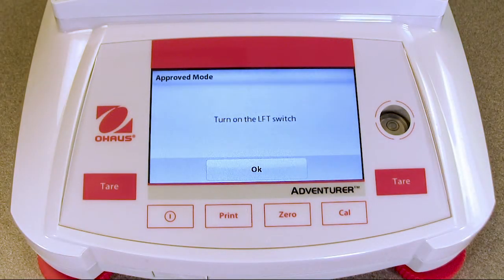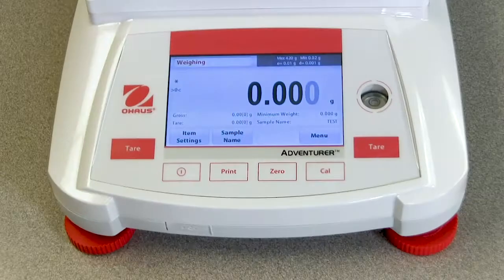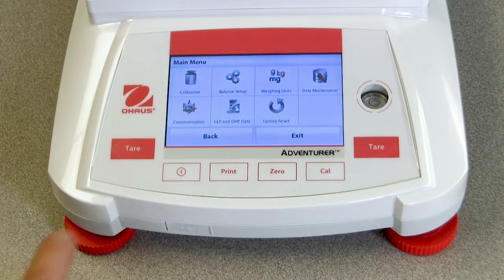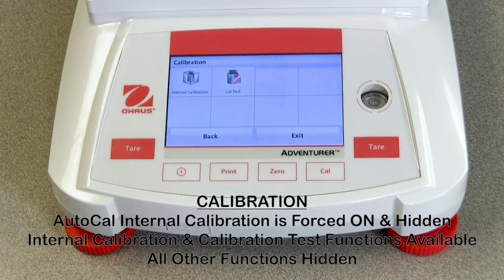The security switch located at the rear of the balance must be in the lock position to set approved mode to on. The security switch must be in the unlock position to set approved mode to off. When the approved mode is on, you will notice the following changes. In the calibration menu, AutoCal internal calibration is forced to on and hidden. Internal calibration and calibration test functions are available. All other functions are hidden.